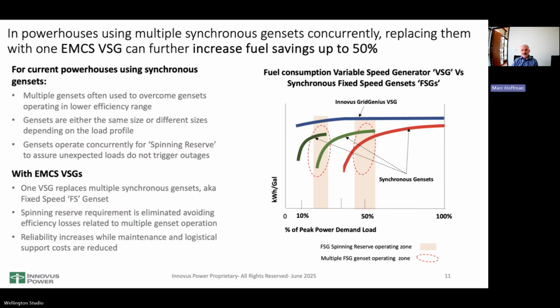So what they typically do, as many of you on the phone know, is powerhouse operators put in 2 or maybe even 3 different gensets in their powerhouse. We've seen some with 4, and they literally turn them on and off during the day over a 24-hour period, depending on where the load profile is at that time, to hit the sweet spot in a given generator.